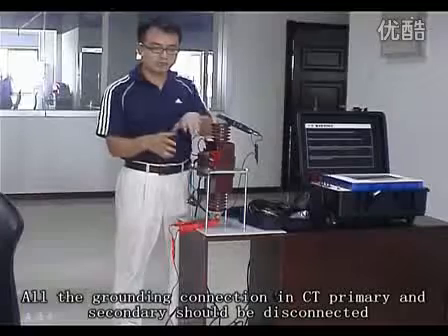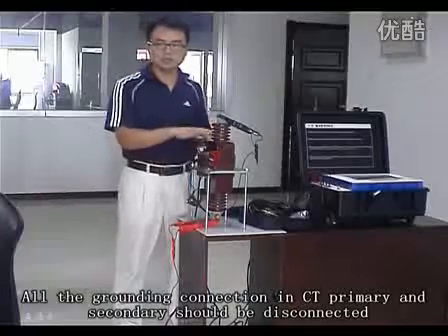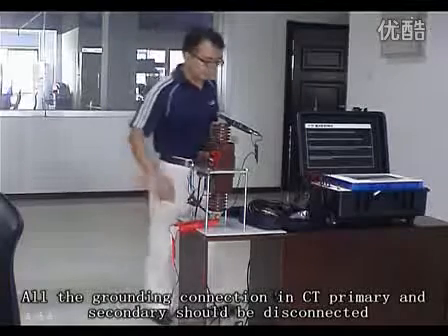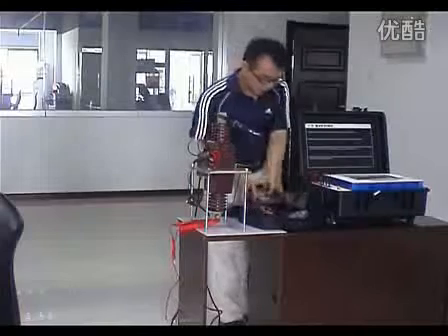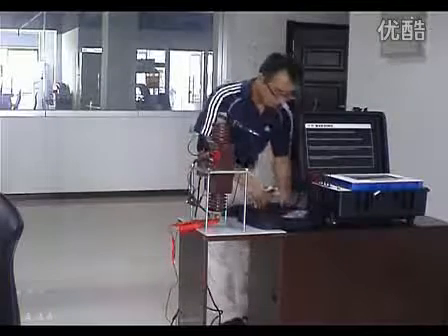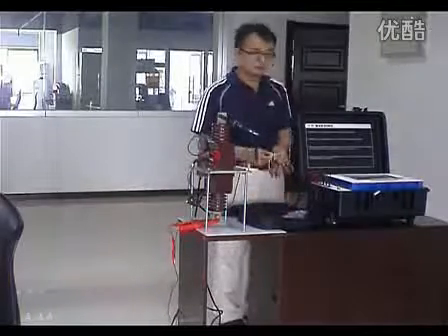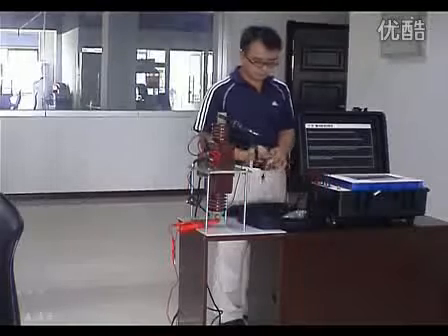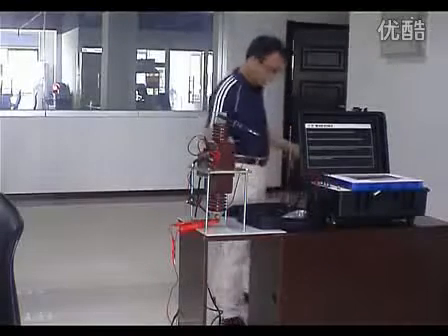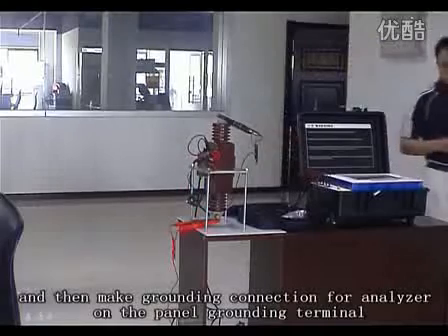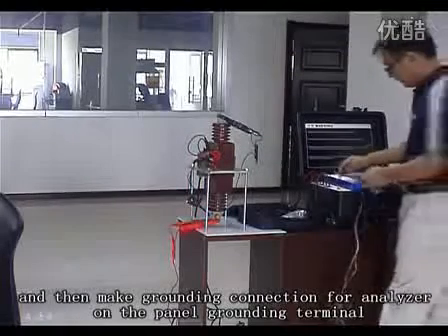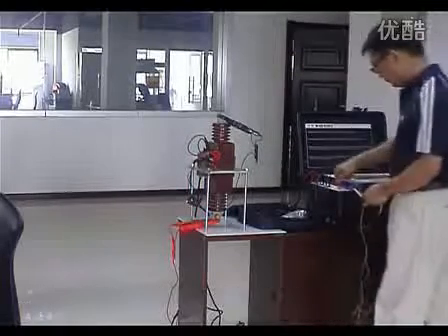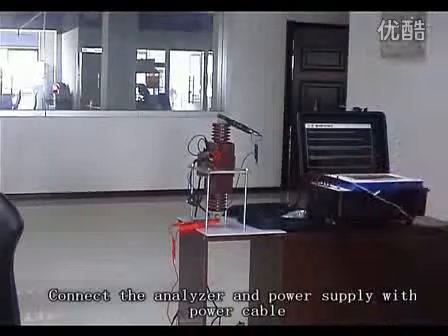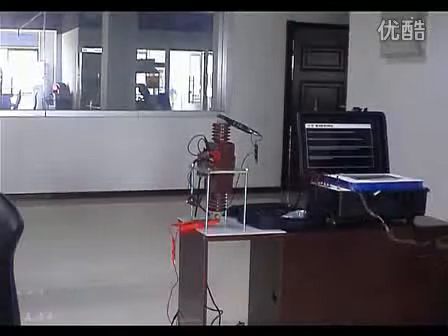All the grounding connections in the CT primary and secondary should be disconnected. And then, make a grounding connection for the analyzer on the panel grounding terminal. Connect the analyzer and power supply with the power cable.